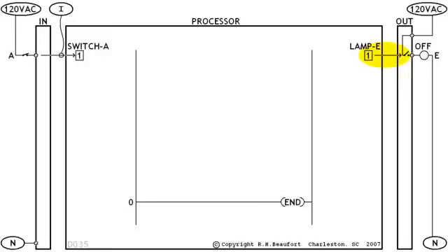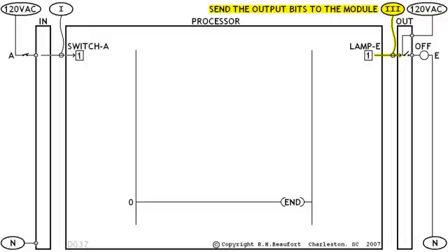And now for the output side. Next, we need to talk about when the transfer shown by this little arrow takes place. Here's the step in the scan cycle that takes care of the transfer, and notice that it's step number 3, not step number 2 the way you might have guessed. The processor does this step several hundred times a second too, and each time it does, it sends the status of the output bits over to the module. Suppose that we stay in slow motion mode and just watch the contacts for a few milliseconds. Nothing changes at all until the processor suddenly comes around to do step number 3.